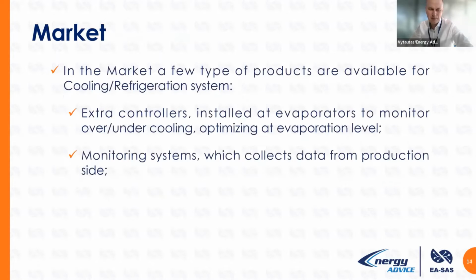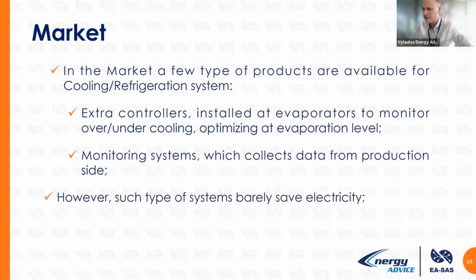So what does the market propose? The market proposes probably two technologies, and our technology would be a third type. One technology is to put PLCs, controllers, on the consumer side, for the cold room for example, and monitor the overcooling and undercooling of your room, and probably save some by not delivering cold or thermal energy to the room. Another type of technology is monitoring: I just monitor something and maybe we would see something. But probably these technologies don't save you electricity, or they save it over a very, very long period, and you never know the real results.